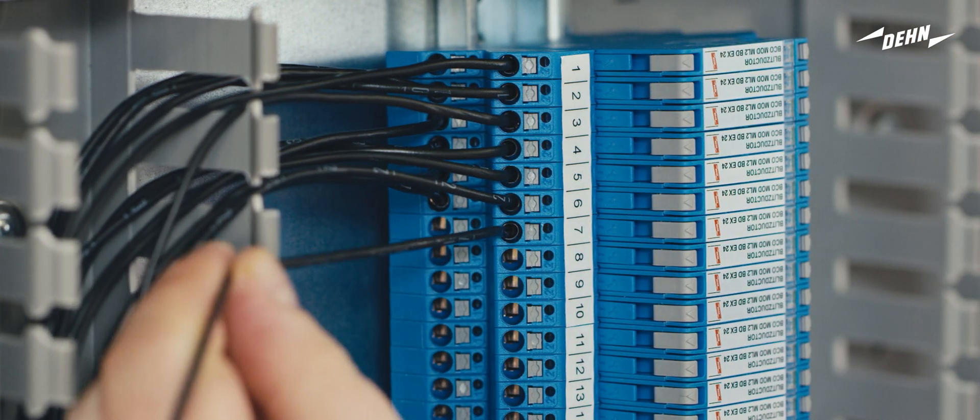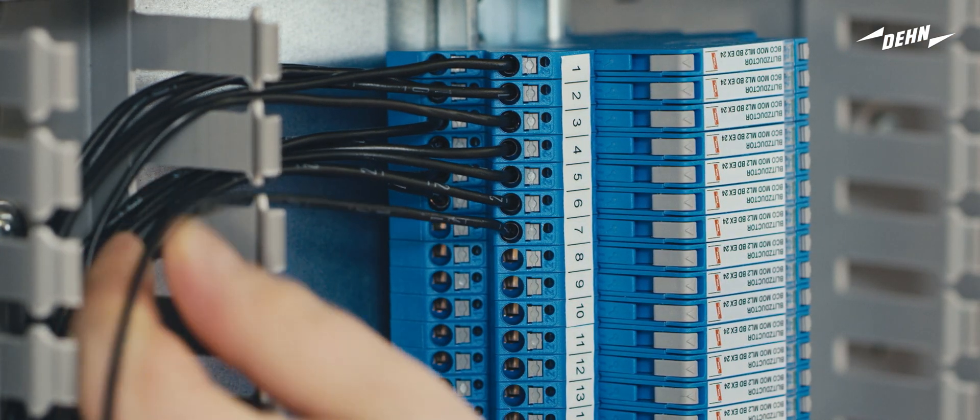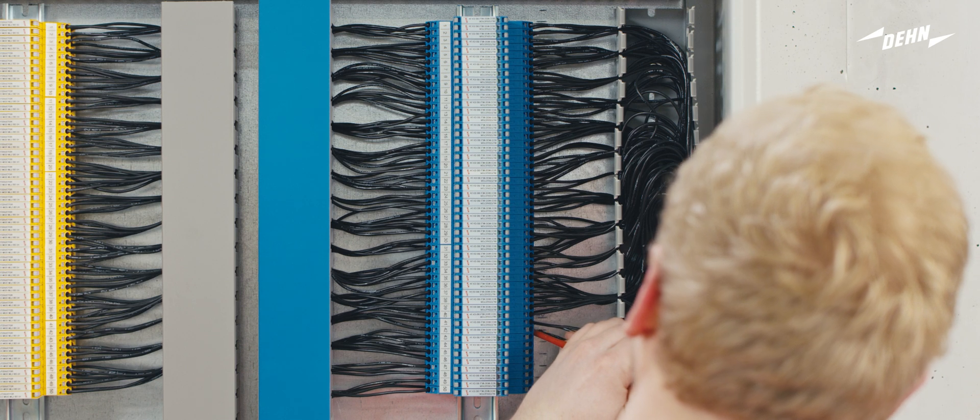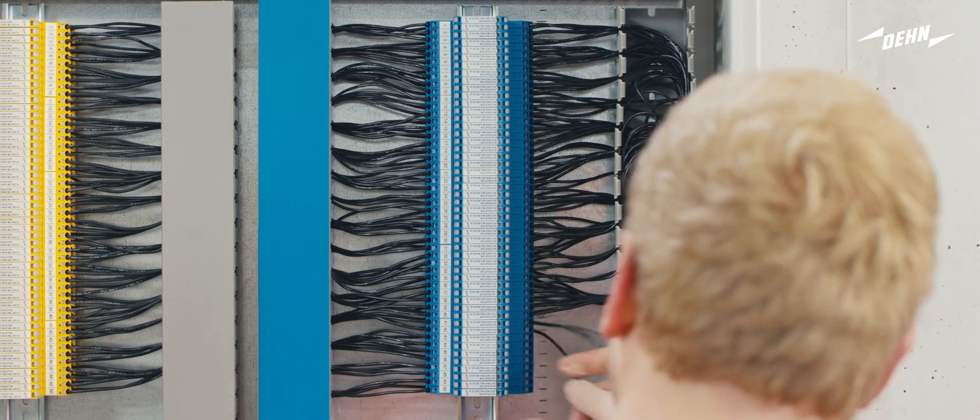Remember that the lines of intrinsically safe measuring circuits must be connected using wire end ferrules on both sides. The push-in buttons also make it easier to install the blue arrestors.